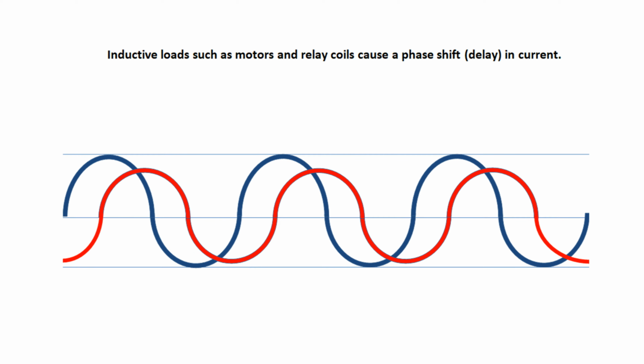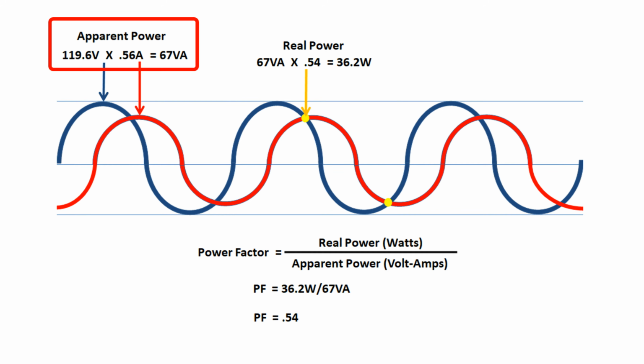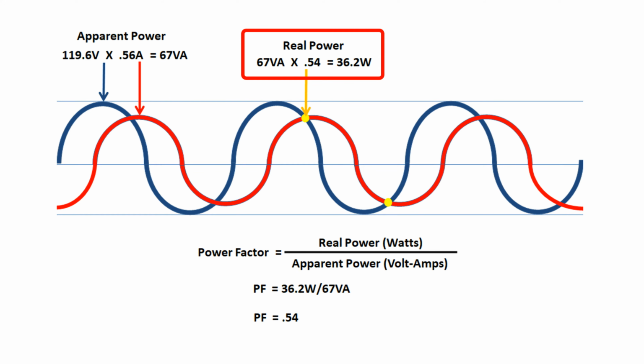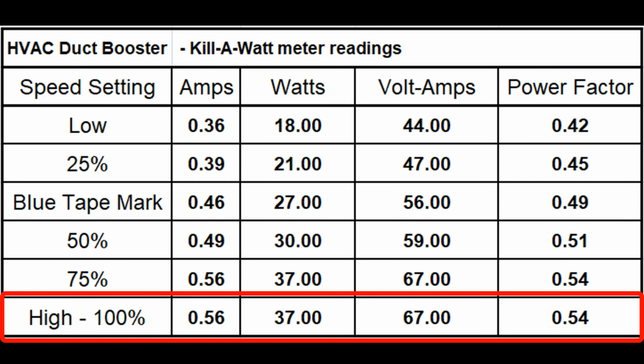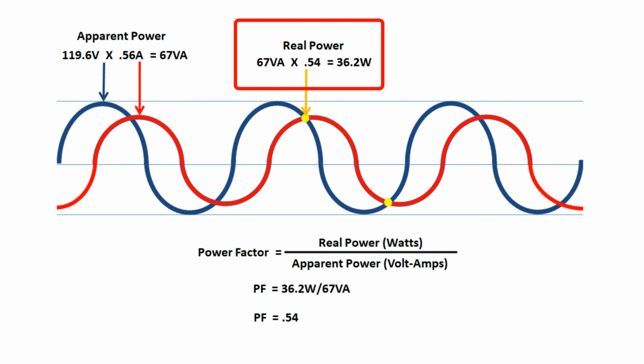It's because inductive loads like motors and relay coils cause a phase shift in the current waveform. Current lags voltage, as seen here. There's a delay in the current. So the apparent power is 67 volt amps, and the real power, which is watts, can be found where the two sine waves intersect. Remember we read a power factor of 0.54? Power factor times volt amps equals watts. Watts are the actual real power being used.